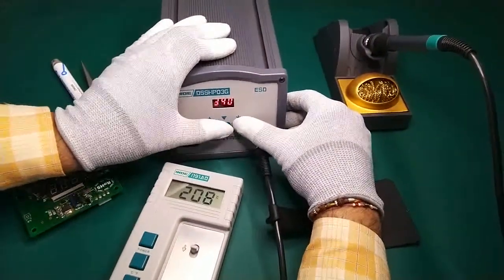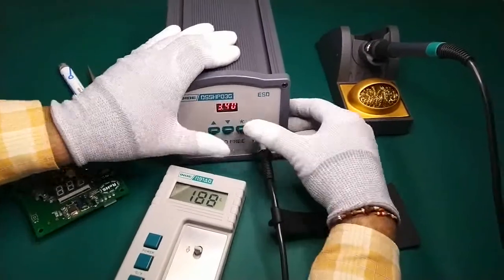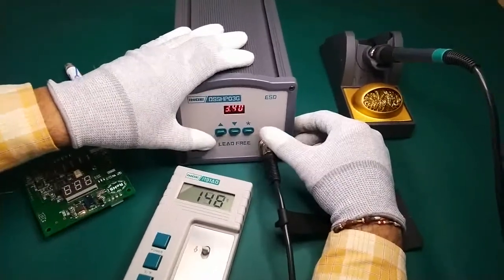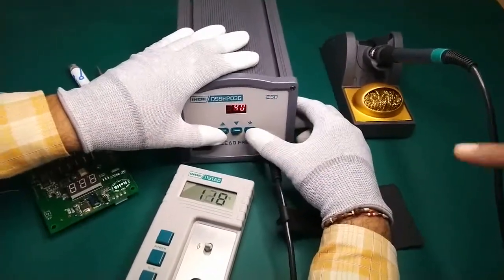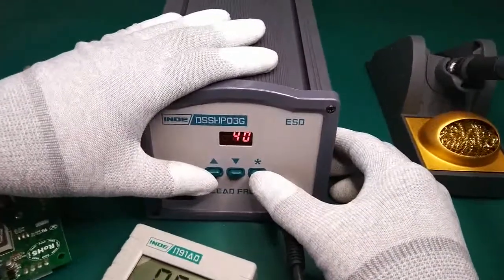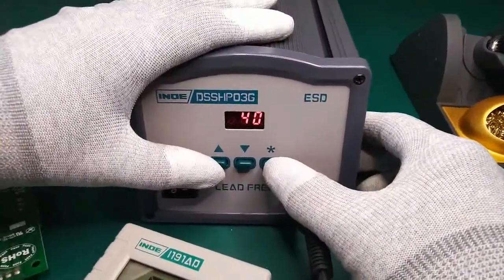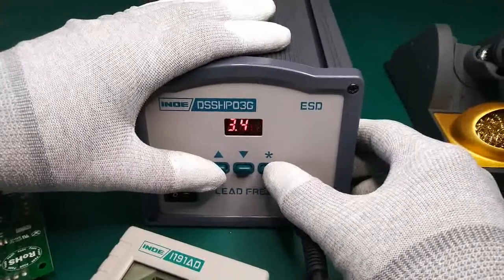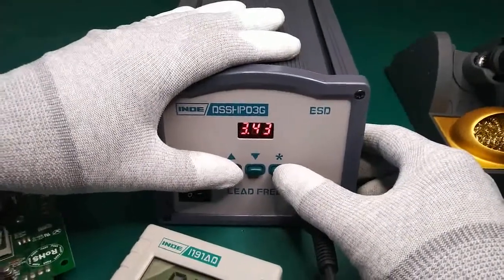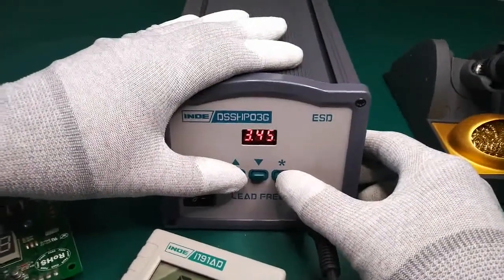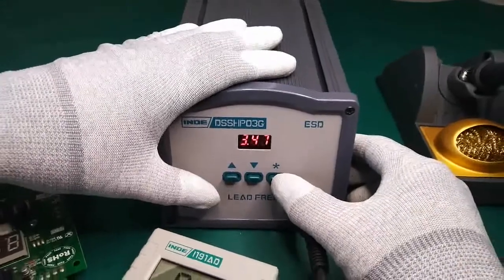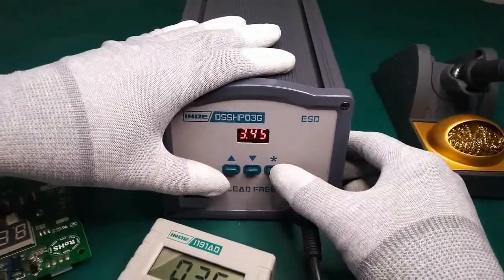Now we will calibrate and match the temperature. First we will press the star button and then simultaneously press the up and down buttons. Now the LED is blinking, and we will move the cursor to the third digit by pushing the star button. Now we will feed in 345, which was measured on the thermometer, and press the star button.